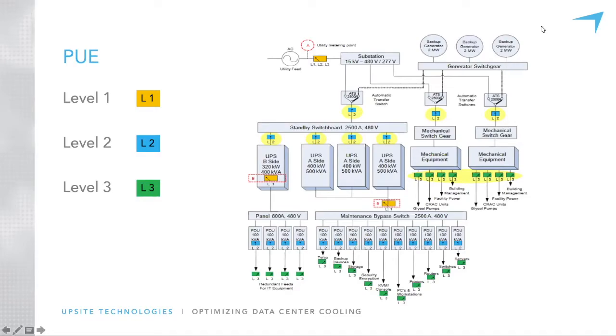But this is just a great schematic drawing that shows us where our level 1, level 2, and level 3 would be. Again, we're looking at the UPS here as level 1. We can see all the areas marked as level 2, and in the data centers I manage and work in, those go out to the floor PDUs. Finally, level 3 is the actual power strips we see within the racks themselves. So again, level 1, level 2, and level 3 — is any one better than the other?